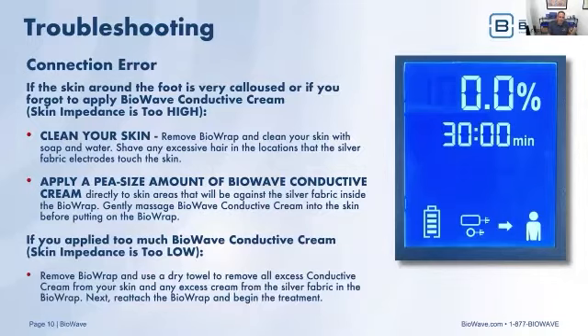If the skin impedance is too high, it may be because the foot is very calloused on the bottom, and perhaps you forgot to apply conductive cream to the skin, or you didn't apply enough conductive cream. Because the skin is so calloused, the device just can't see the attachment, the conduction between the silver fabric and the skin, because the resistance or impedance is too high. In that case, you need to remove the BioWrap and clean the skin thoroughly with soap and water.